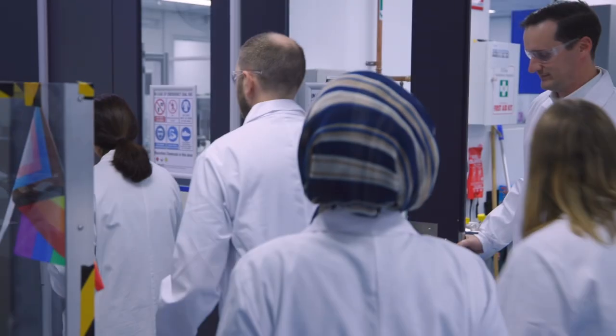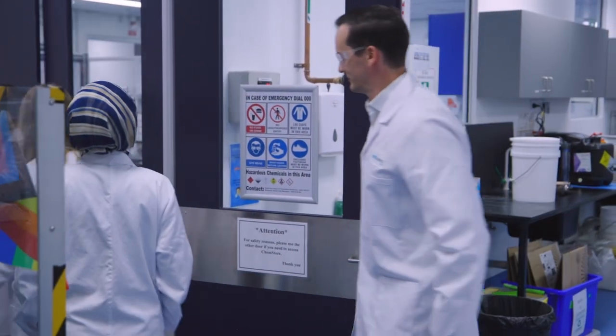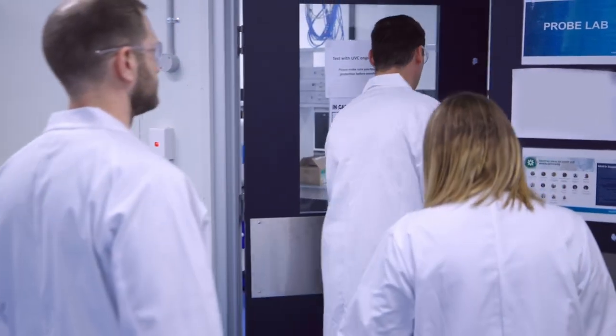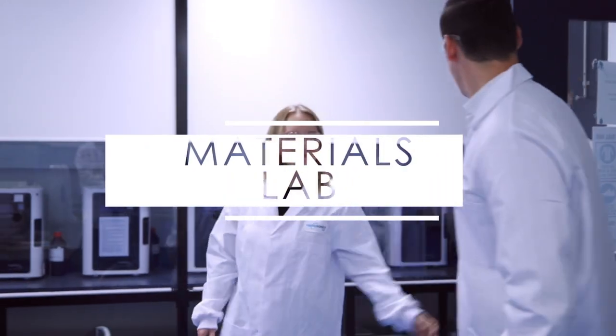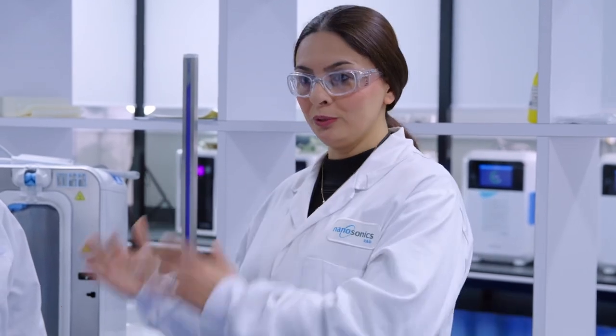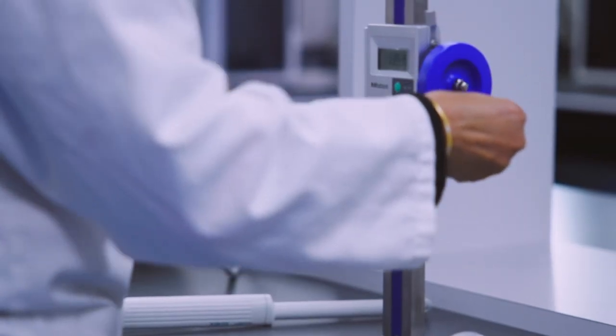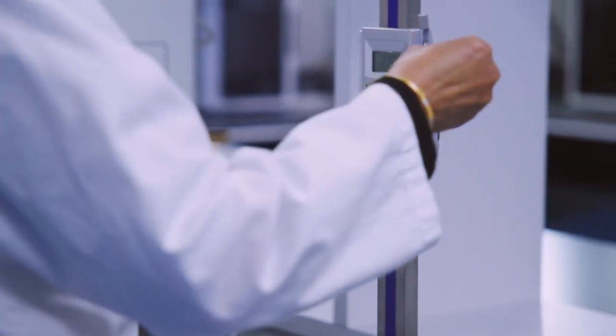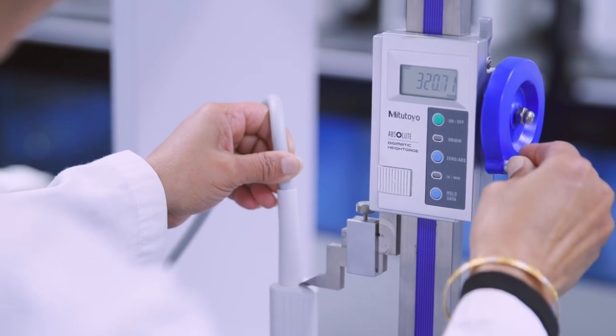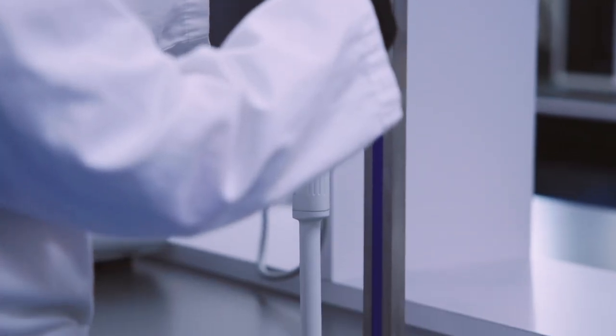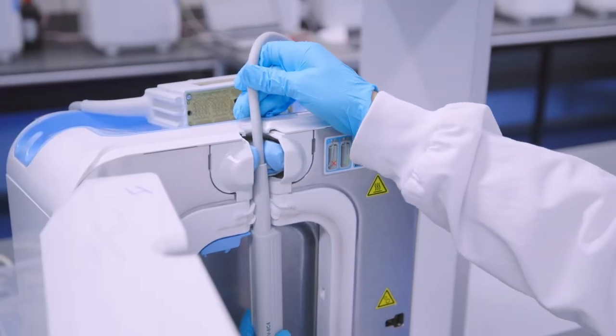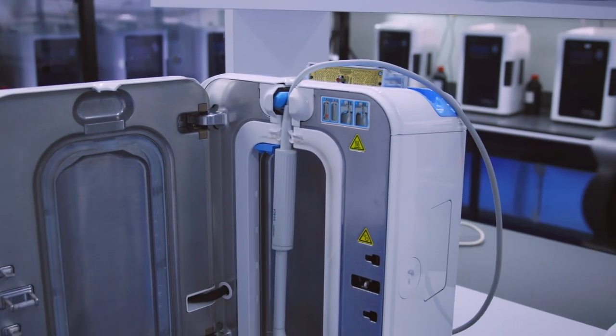A critical step in the Nanosonics probe compatibility program is making sure the Trophon 2 does not damage ultrasound probes. So we went to the materials lab to see their process for ourselves. This is where we test the probe for its life cycle, making sure that from day 0 to the end of the life of the probe, the technology is safe for it. Firstly, we measure its dimensions to make sure that it fits into the Trophon envelope, and then we do a fit test. We hang the probe inside the device, making sure that it fits properly.